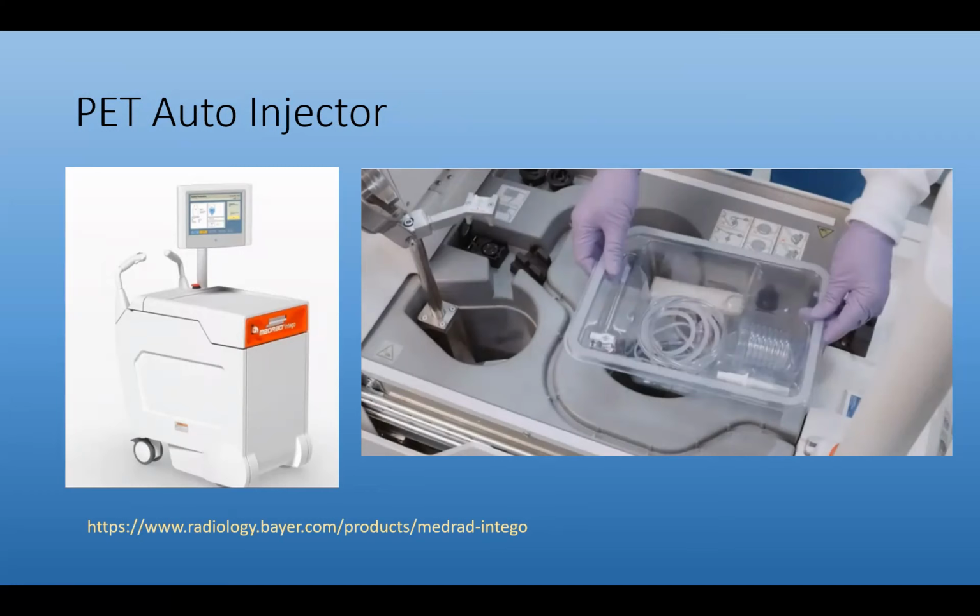But when they actually did the research, they were surprised to find that their left hand was actually receiving more dose than the right hand. And that was because the left hand was usually holding the pig that had the radiation in it. And so they've since made some changes in their setup, and they have a device that sort of holds the pig for them so that they can minimize their exposure.